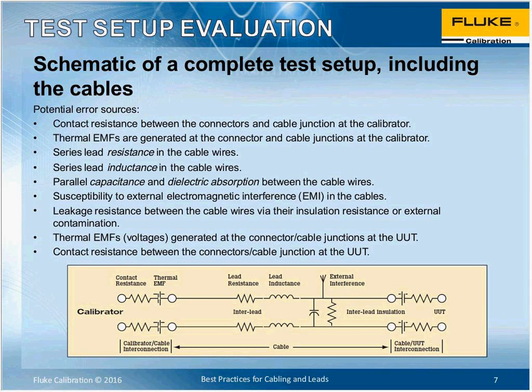Okay, when you look at the test setup, when you're calibrating a DMM or doing a transfer measurement or whatnot, there are a couple of things you have to be aware of when making precision measurements. The diagram that I show on the slide here is a basic schematic of all the different error sources that could potentially affect your measurement, and it varies with the type of measurement that you're trying to obtain, but just a couple of notes here.